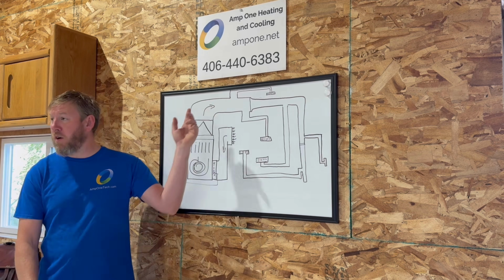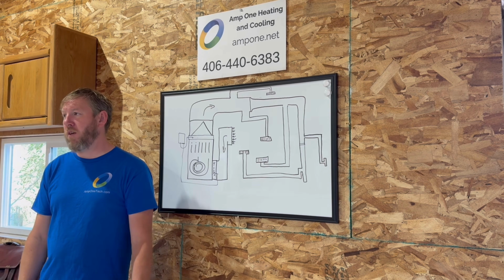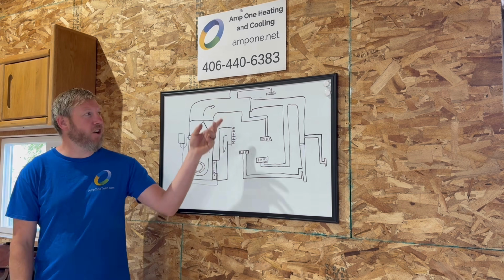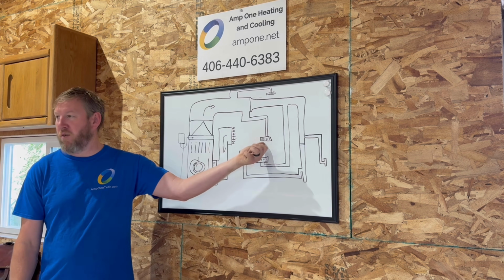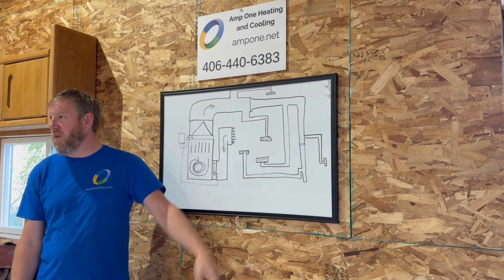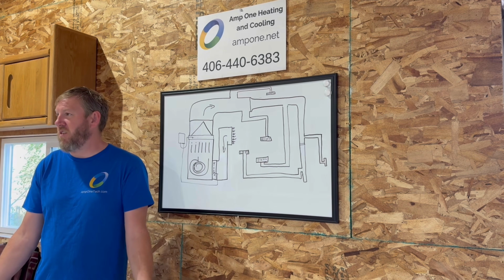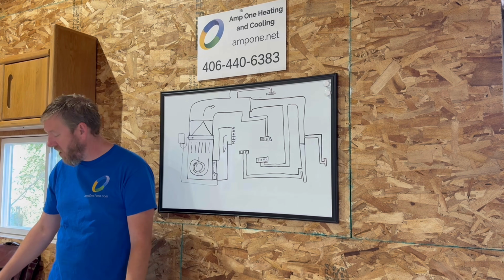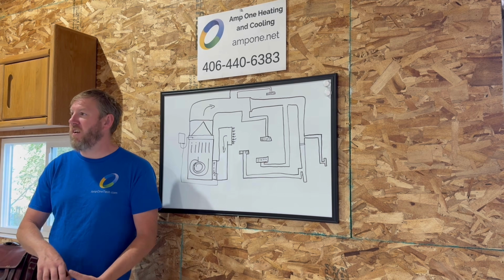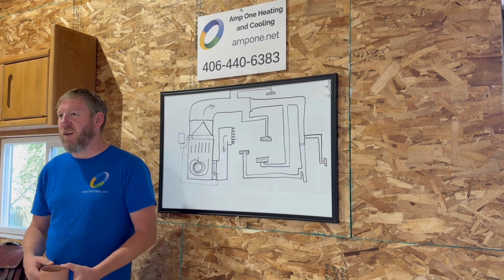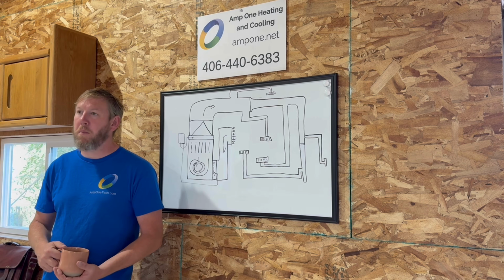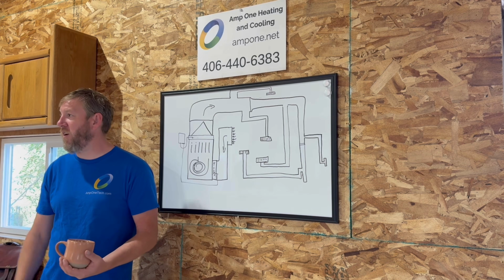And then wrapping the ductwork. Come summertime, it's losing that heat, and then all of a sudden the air blowing out of your vents is no longer at 55 degrees, it's at 70 degrees. That doesn't do anybody any good, it doesn't cool anything. And on top of that, it can condensate and cause all kinds of issues. So that's part of the wrapping, even though it's a pain and it's not fun, that's why we do it.